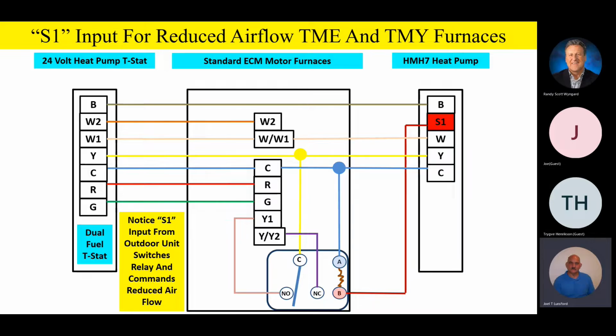This outdoor unit's going to modulate down as it starts getting milder outside, or the temperature inside the space starts getting close to set point. It's going to modulate down. It's going to reduce the airflow, keep the unit running a little bit more, provide wonderful humidity control, and just a level of comfort that's unattainable with a single stage product. Any questions or comments before we continue with some variable speed products, air handler and furnace, to be specific here shortly? Any questions or comments?